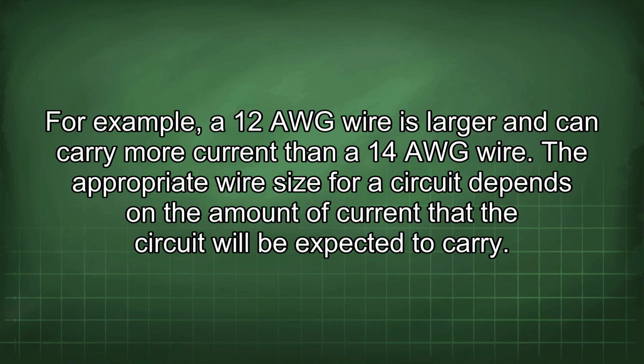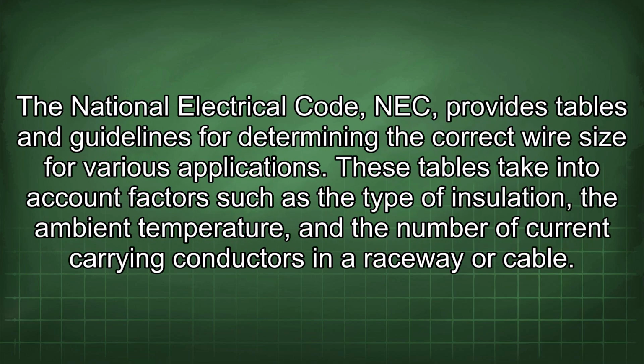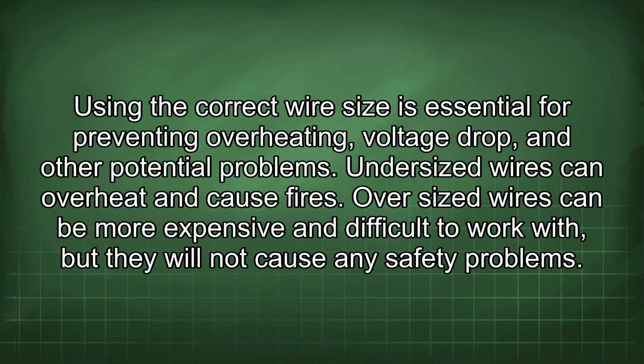The appropriate wire size for a circuit depends on the amount of current that the circuit will be expected to carry. The National Electrical Code (NEC) provides tables and guidelines for determining the correct wire size for various applications. These tables take into account factors such as the type of insulation, the ambient temperature, and the number of current-carrying conductors in a raceway or cable. Using the correct wire size is essential for preventing overheating, voltage drop, and other potential problems.